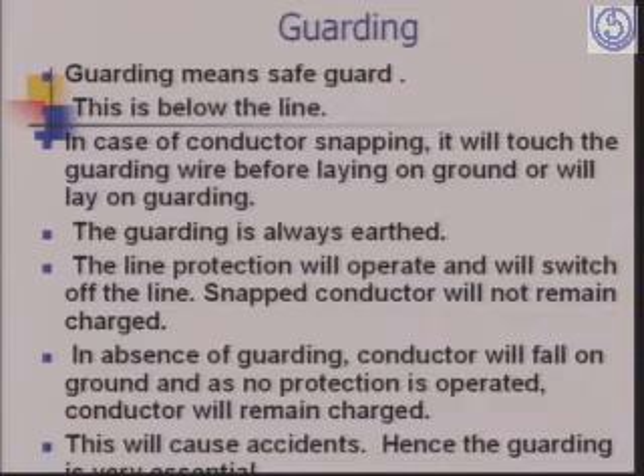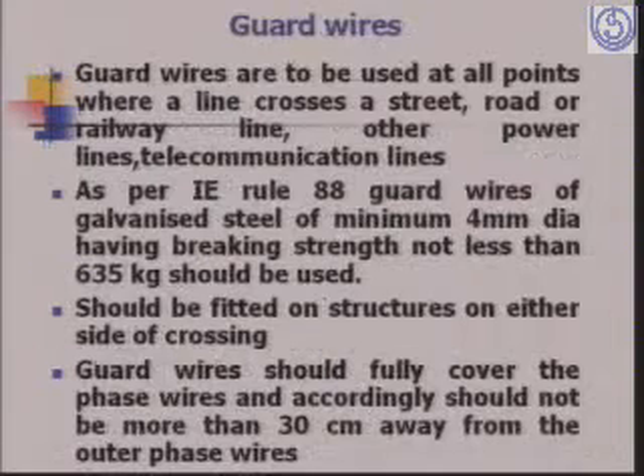Hence, guarding of especially the 11 kV and 33 kV lines is very important. That is why guard wires are provided. The guard wires are to be used at all points where a line crosses a street, road or railway line and other power lines or telecommunication lines. As per IE Rule 88, guard wires of galvanized steel of minimum 4 mm dia having breaking strength not less than 635 kg should be used. They should be fitted on structures on either side of the crossing. Guard wires should fully cover the phase wires and accordingly should not be more than 30 cm away from the outer phase wires.